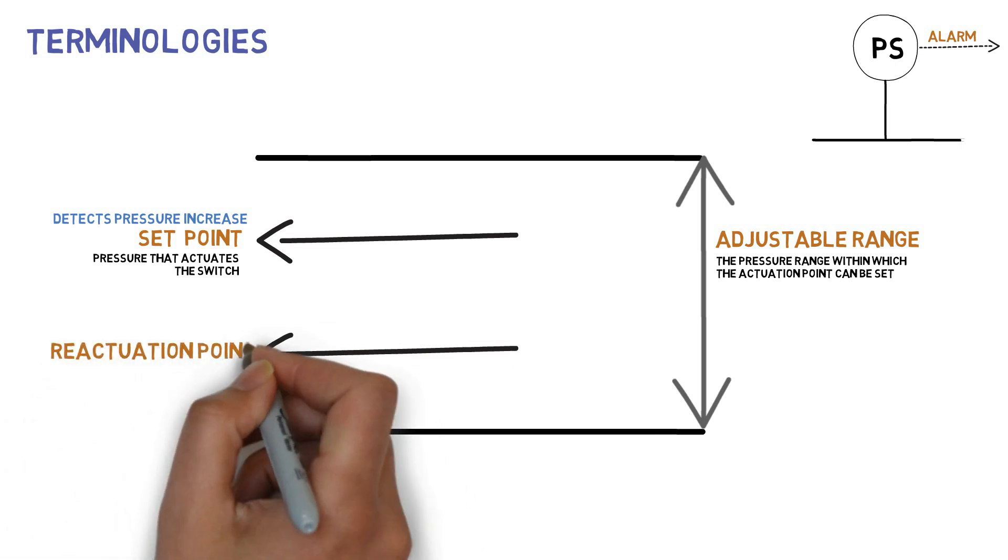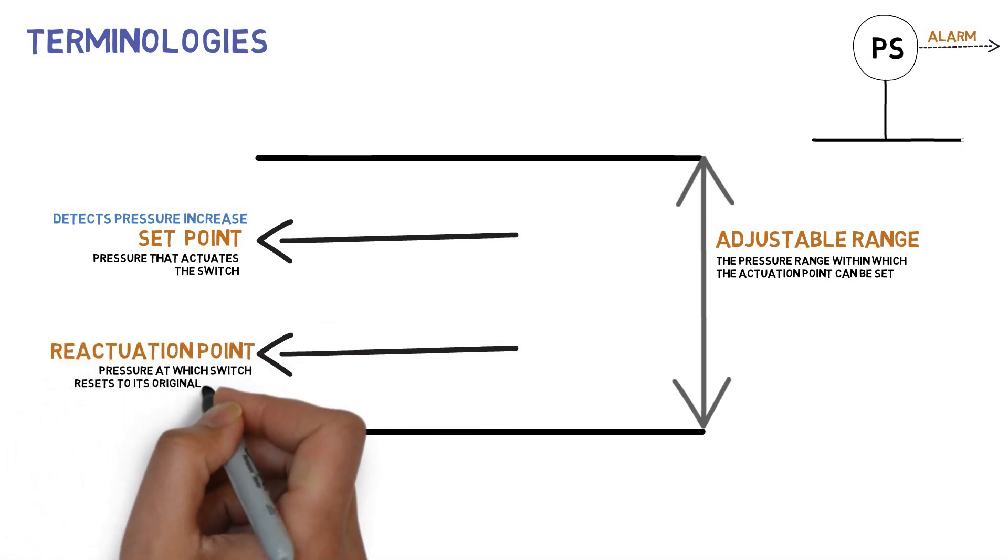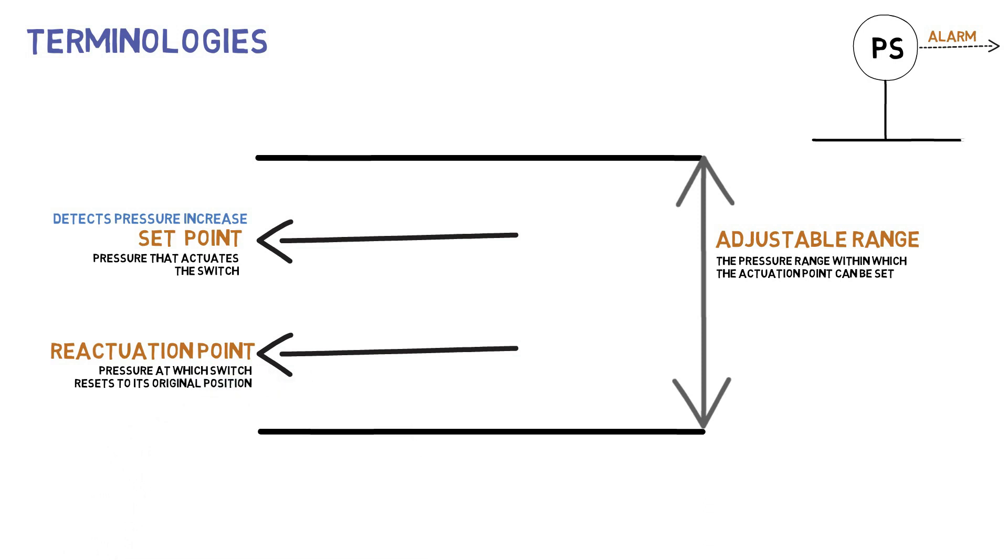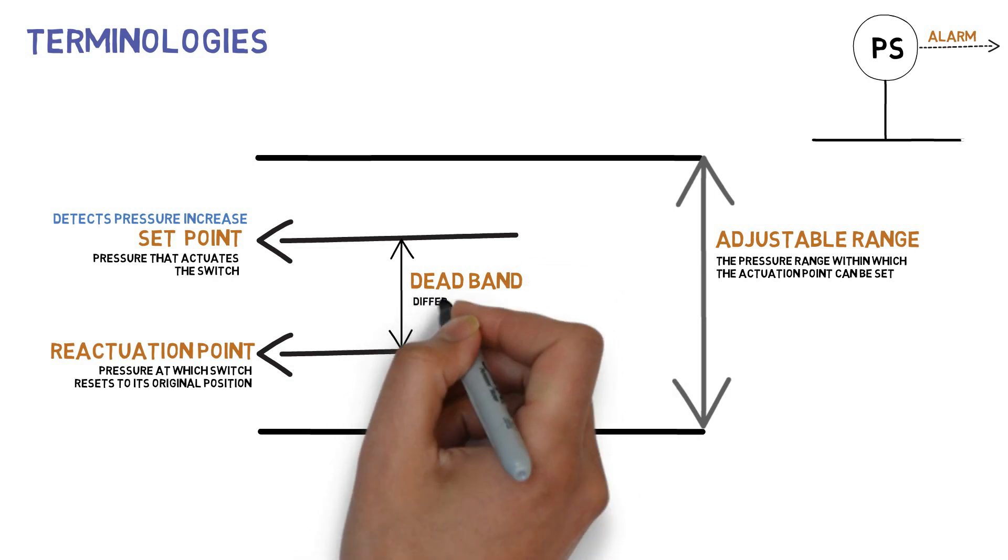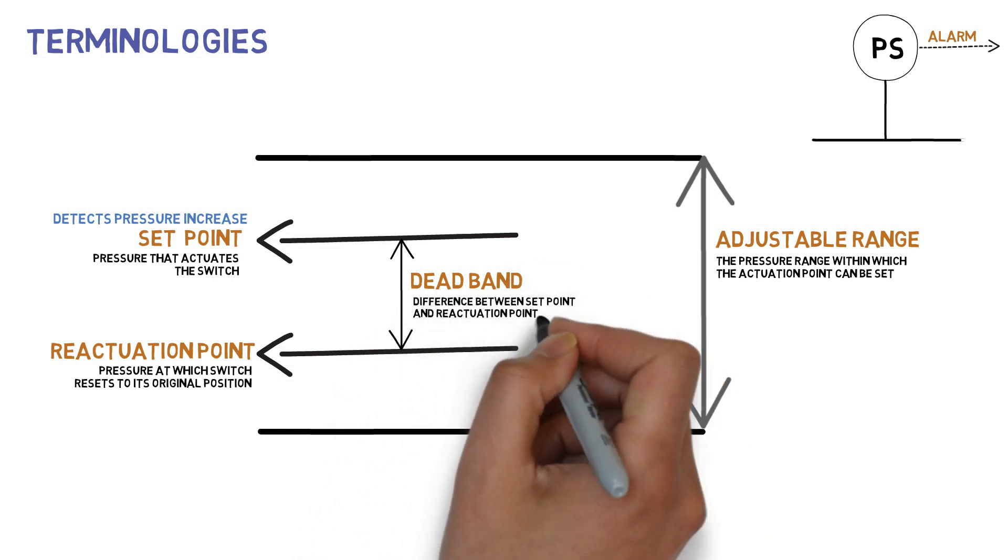Reactuation point is the pressure at which the switch resets to its original position. Dead band is the difference between set point and reactuation point.